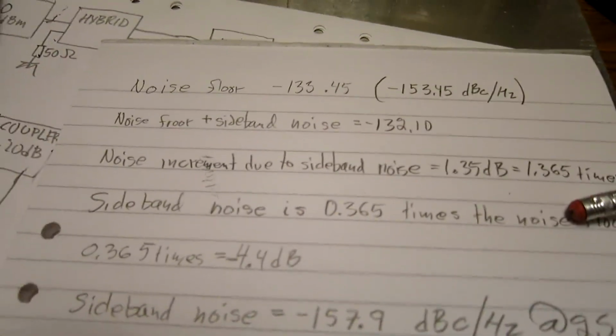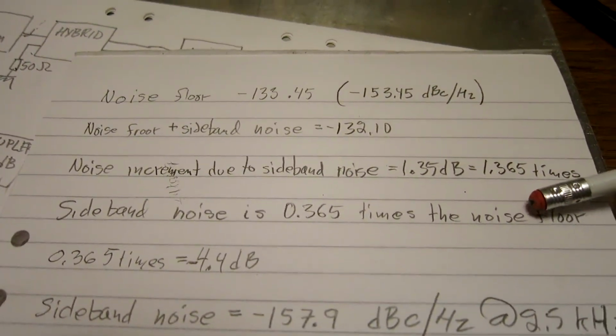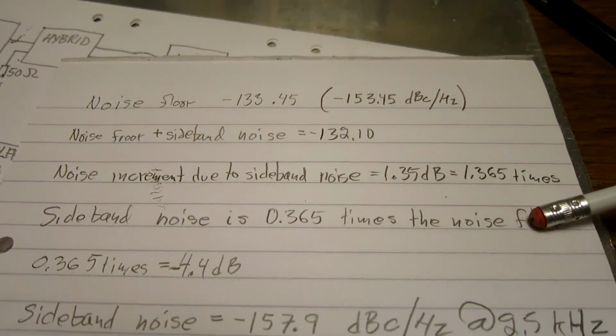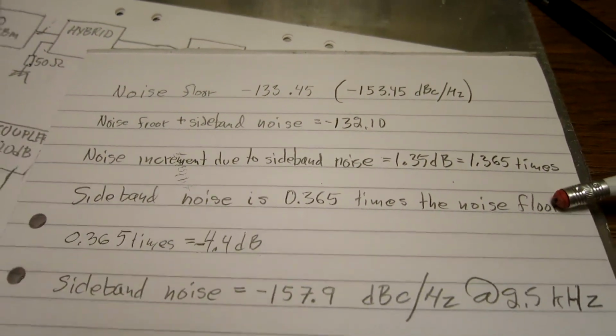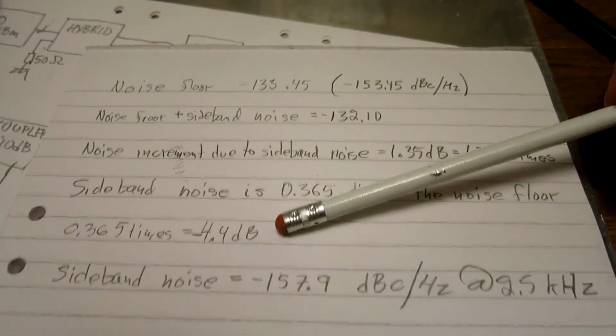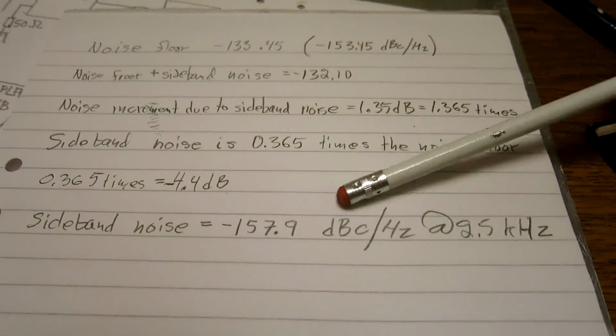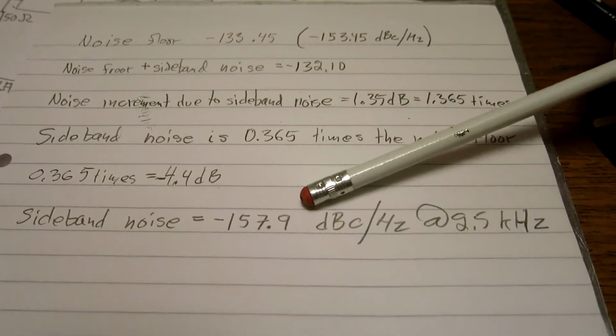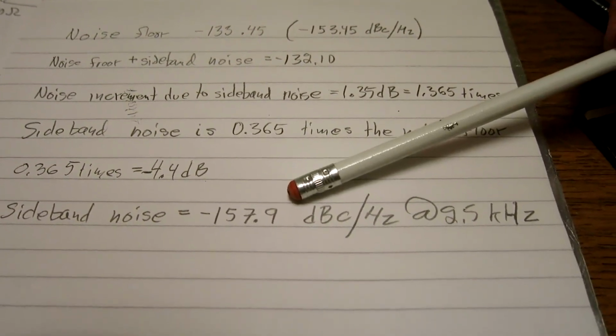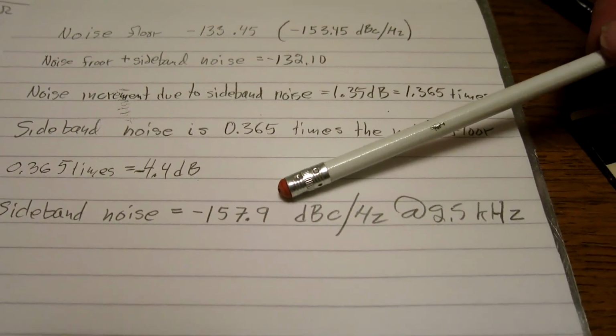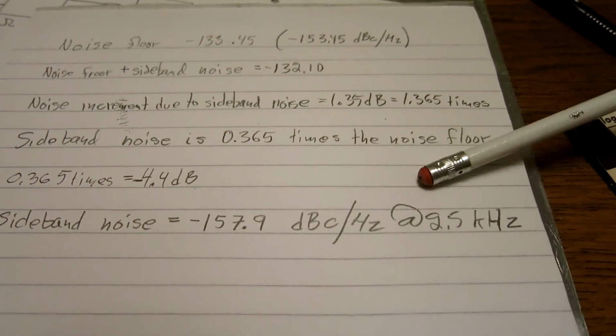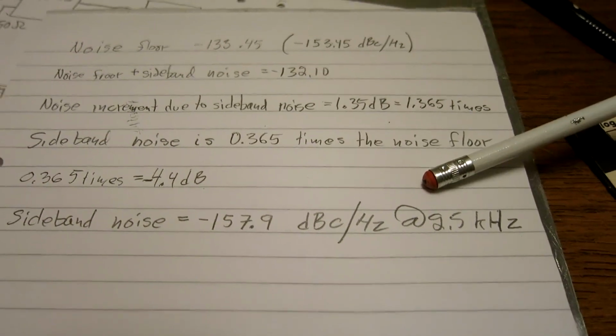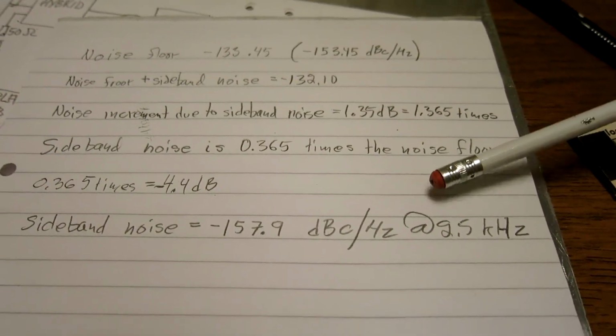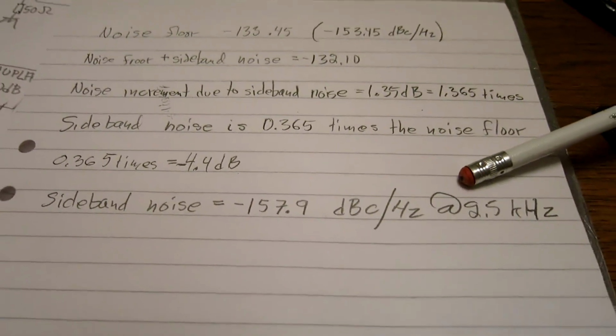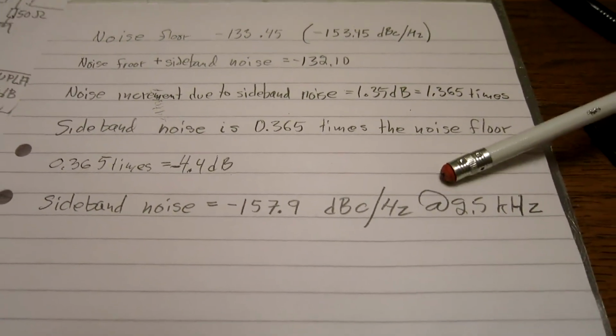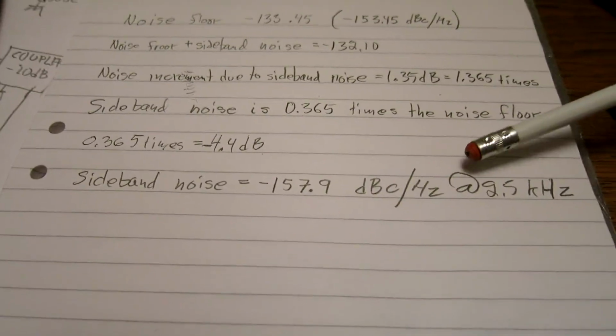The sideband noise is then 0.365 times the noise floor. And that's minus 4.4 dB. So what I found is the sideband noise is minus 157.9 dBc per hertz at 2.5 kilohertz. And this is the sum of all sources of sideband noise, the two oscillators and anything else that might generate sideband noise.